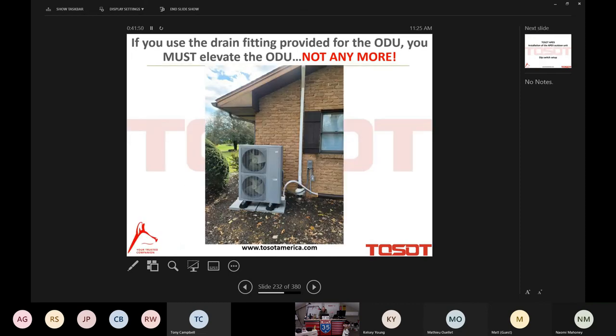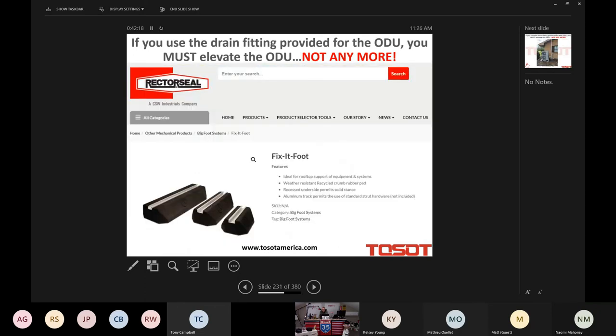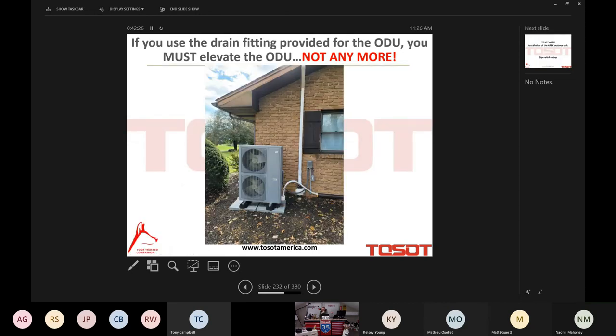I did it for one reason. You can see this is my home. You can see the outdoor unit is on a traditional pad, 2 inches in depth or height, I should say, no big whoop there. I didn't have a need to use that fitting, but I did want to get the outdoor unit above a typical snow line. And also, they work as a wonderful added benefit for vibration. These are solid rubber curbs, and they act as wonderful vibration isolators.